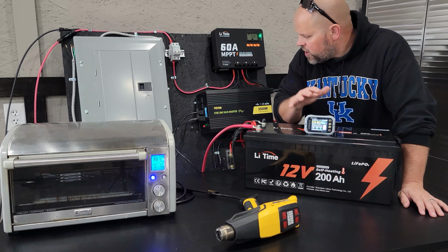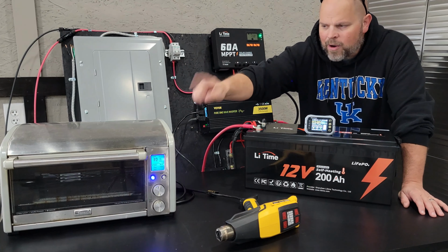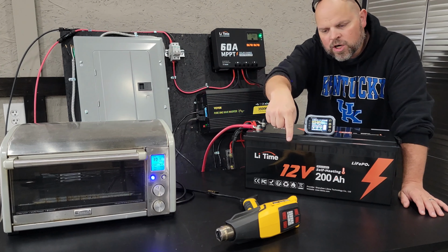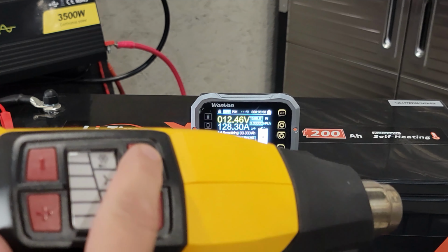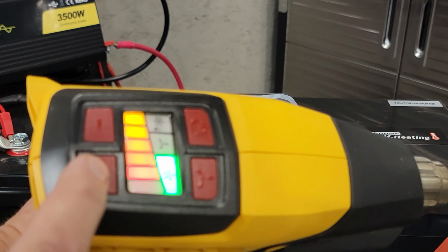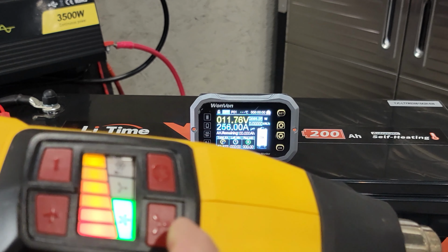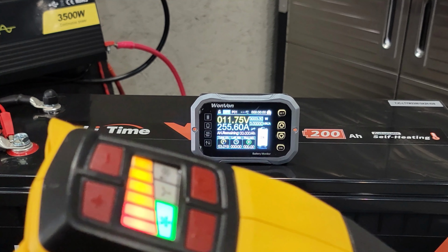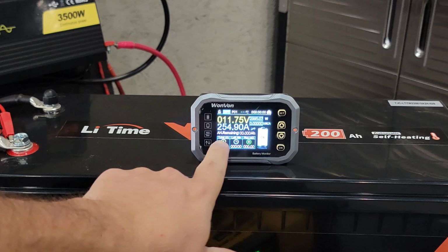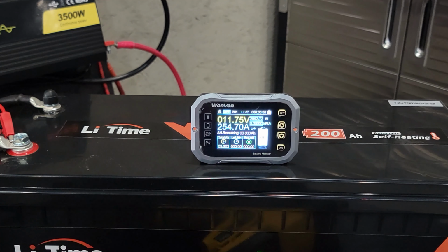Now that we have the shunt set up and the inverter turned on, I'm going to turn the oven on first, then we'll turn on the heat gun, and we're looking for this to go well over 200 amps to shut down the BMS in the battery. Now we'll turn the heat gun on, all the way up. And we're running at 255 amps.